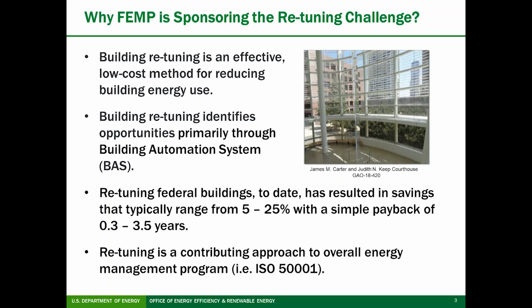Why is FEMP sponsoring this challenge? Retuning is really an effective low-cost method for reducing energy. Retuning identifies the opportunities through the BAS, or the building automation system. We have seen from previous retuning initiatives savings between 5, and actually your slide says 25, but what we've seen is higher than that. I think we've reached 30% in some cases, with a simple payback from several months to 3.5 years. That's really a very quick payback.